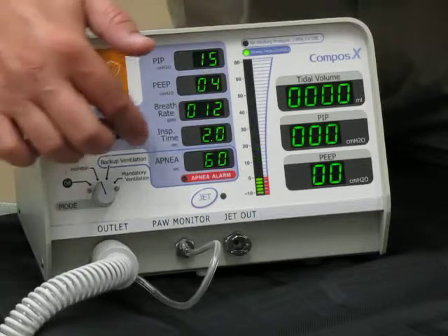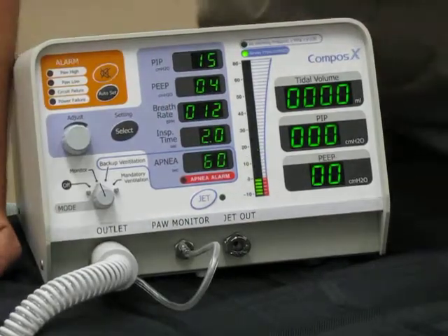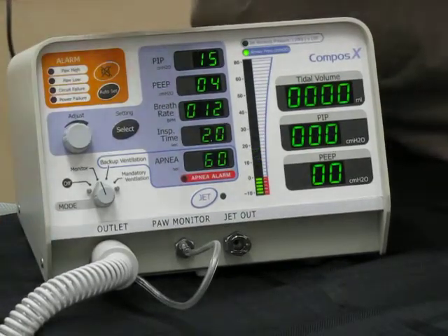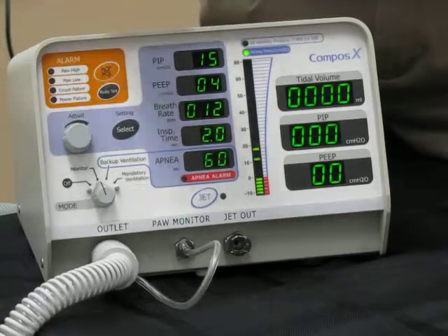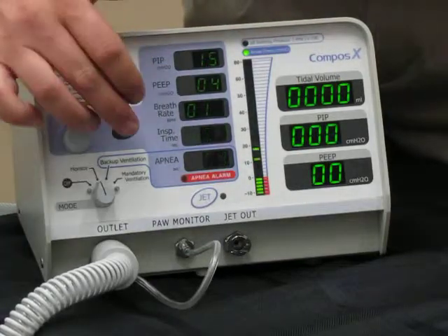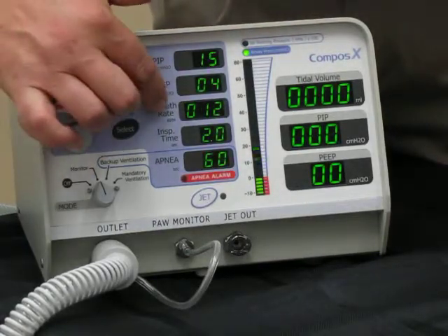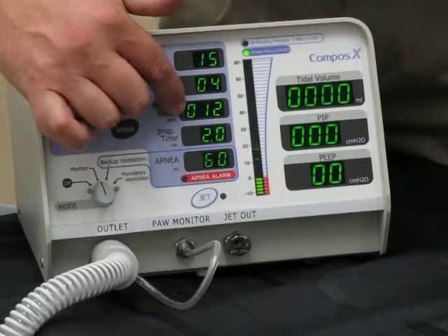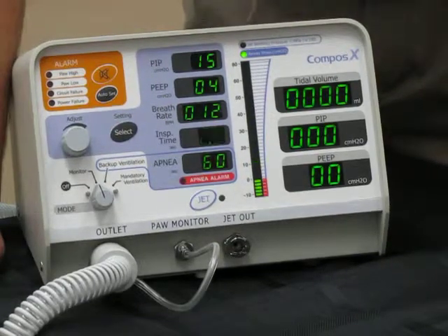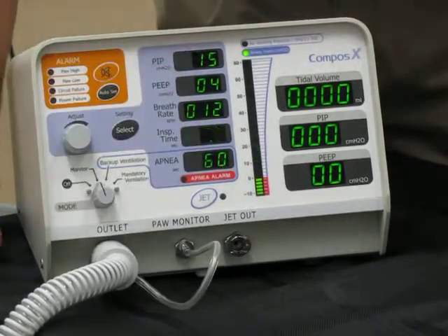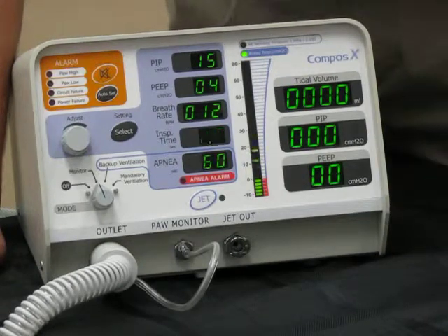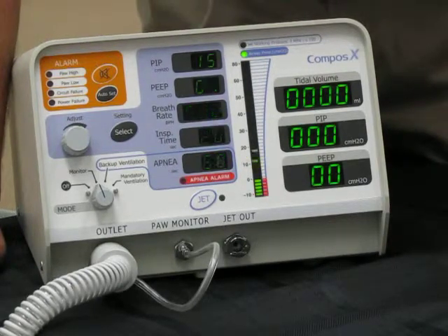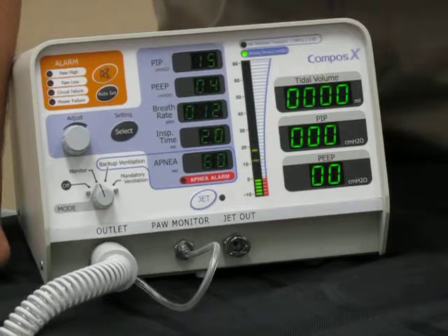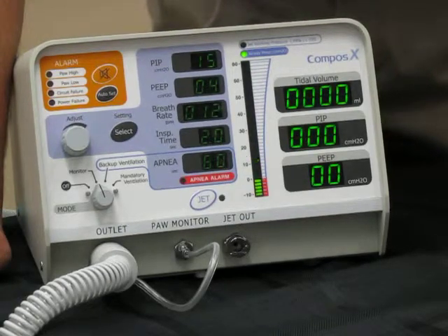And when we talk about inspiratory time, what we're talking about is the time for each breath that the unit delivers the breath. Then the extra time is the expiratory time. So if I have my system on a breath rate of 12, that's a breath every 5 seconds. So 2 seconds of that is going to be a breath, and the other 3 seconds is going to be exhalation. And in that we have about a 1 to 1.5 inspiratory expiratory time.